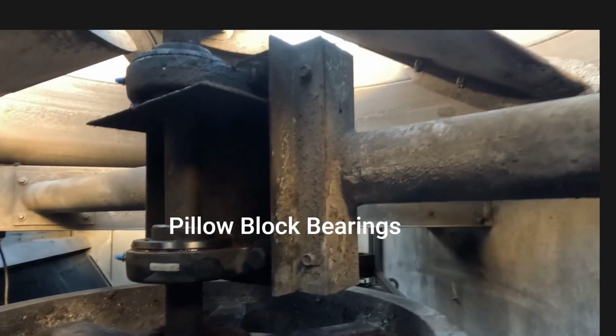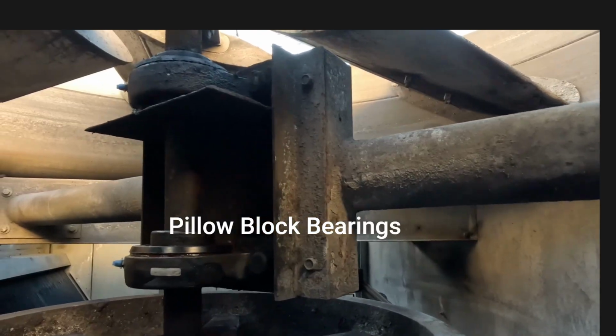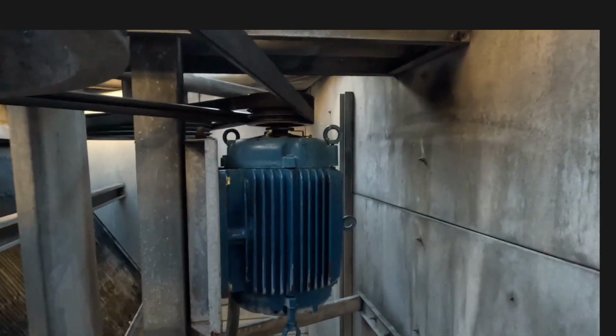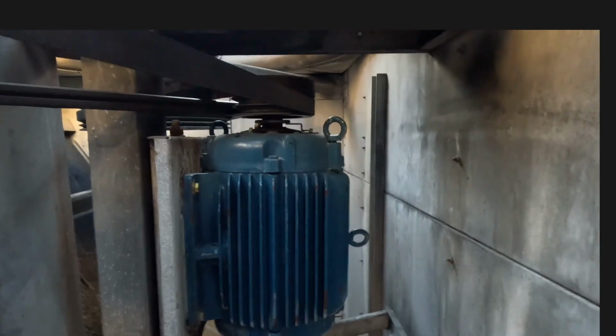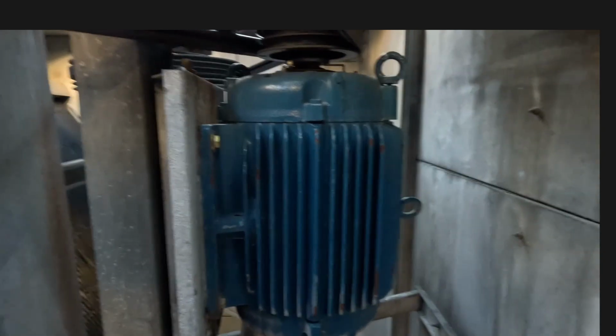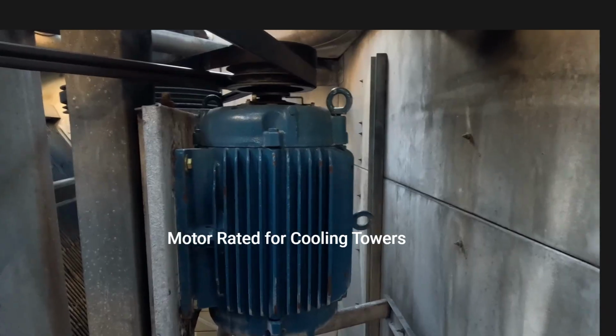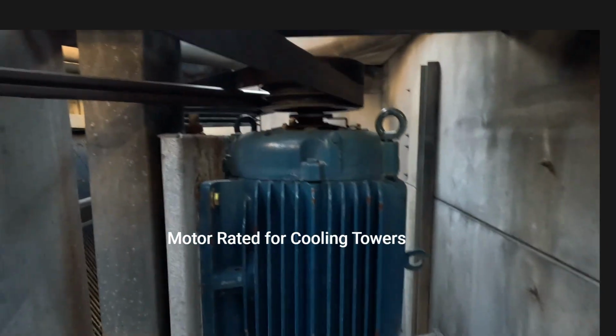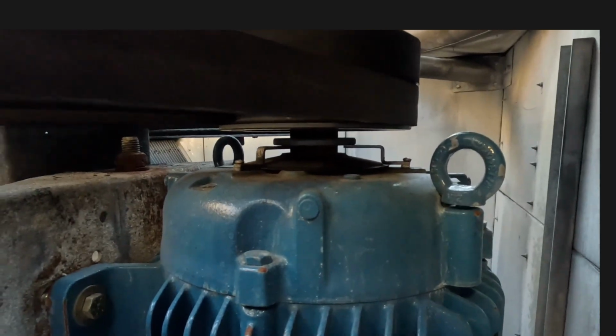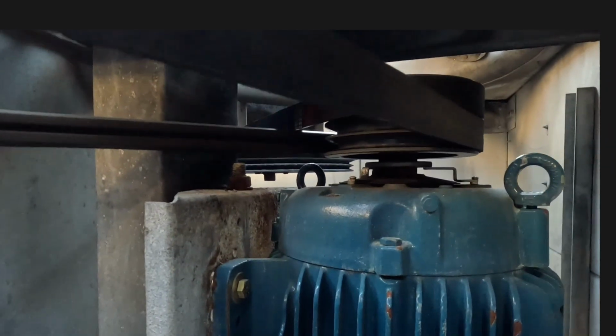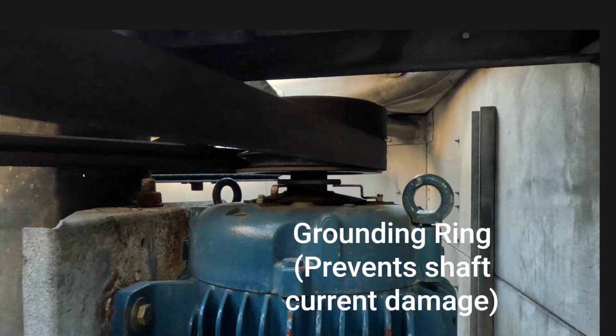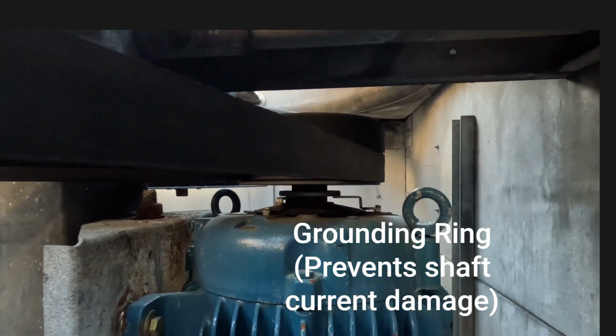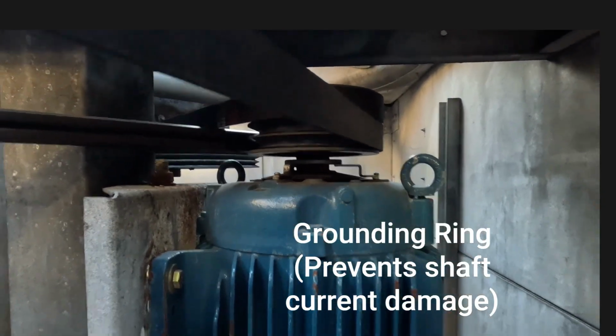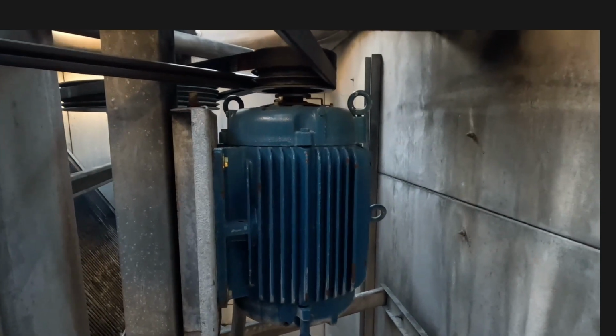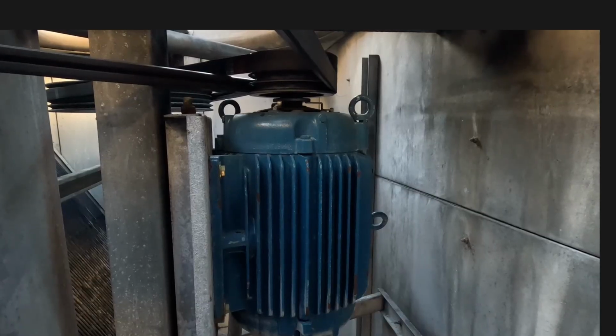So currently filming this on my GoPro 11. So I carry it on the job sometimes just so I can document everything that I see. You can see that's the motor. So this is what we refer to as a motor rated for cooling towers. It's all sealed. You can see it has a little cover up top so no water gets inside of it. It does have a grounding ring to prevent the shaft currents from deteriorating the bearings inside this motor. The motor we replaced about a year ago, so it's still working like a champ, right?